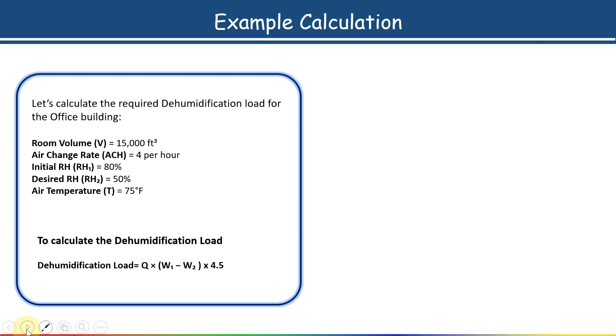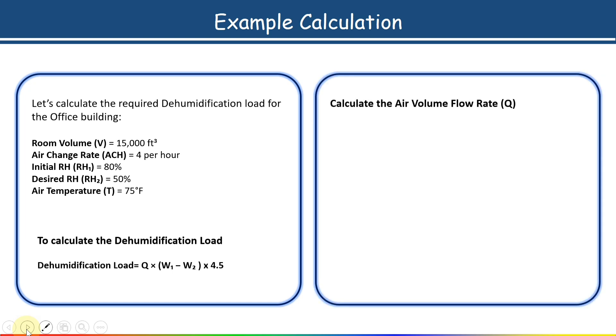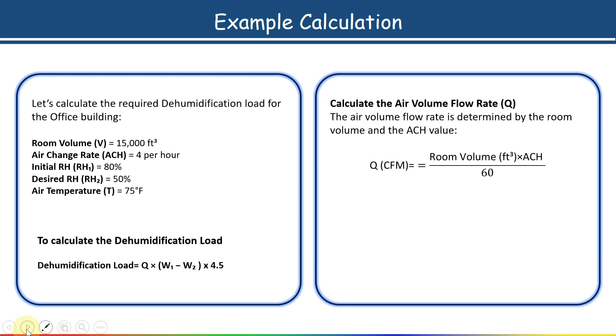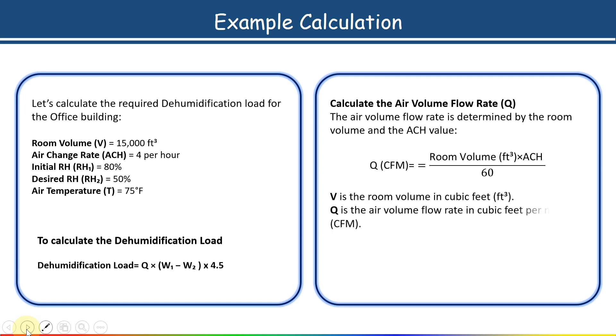To calculate the dehumidification load, the first thing is the air volume flow rate. Using the formula with room volume 15,000 cubic feet and ACH of 4 for the office building from the table, substituting these values gives us 1,000 CFM (cubic feet per minute).